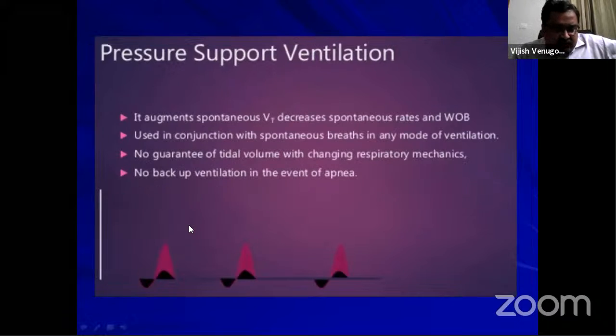You can see here in the bottom, when pressure support is applied, there is an increase in the pressures that are delivered. So it augments your spontaneous tidal volume, and it decreases the spontaneous rates and work of breathing. It is used in conjunction with spontaneous breaths, but very important to remember that there is no guarantee of tidal volume with changing respiratory mechanics. There is no backup of ventilation in the event of apnea.